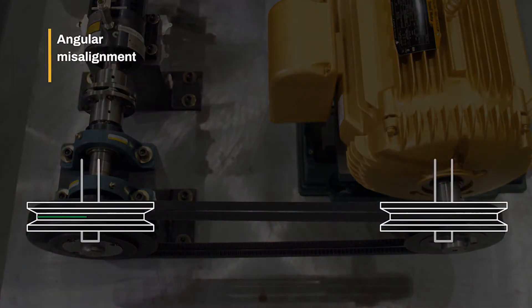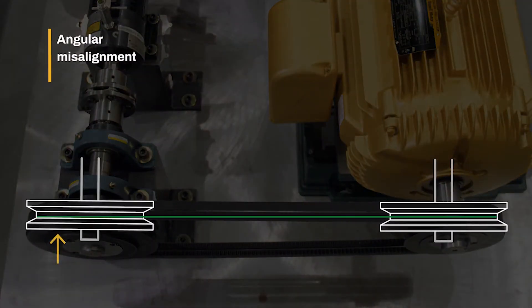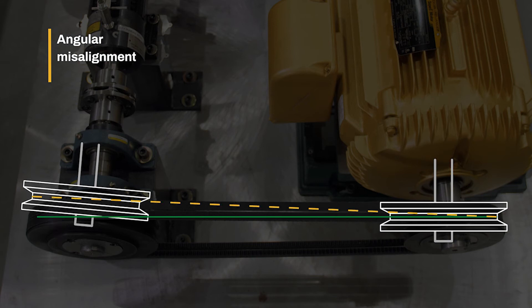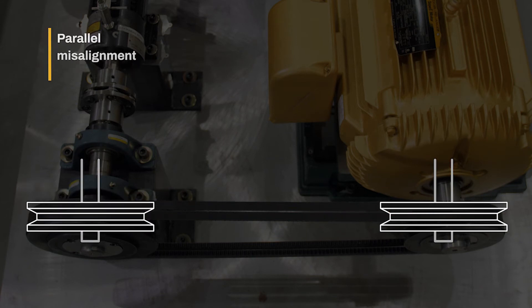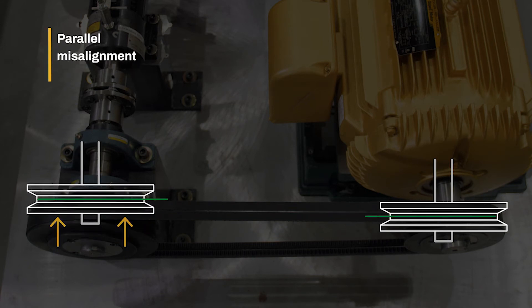Angular misalignment occurs when a sheave is rotated, creating an angle between the center lines of each sheave. Parallel misalignment occurs when the shivs are offset from each other, creating a physical gap between the center lines of each sheave.